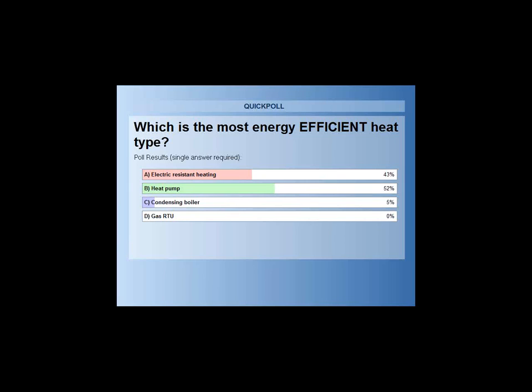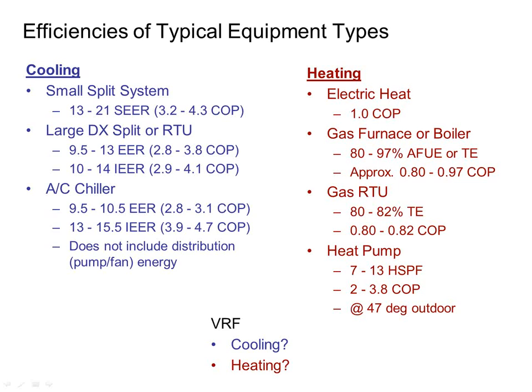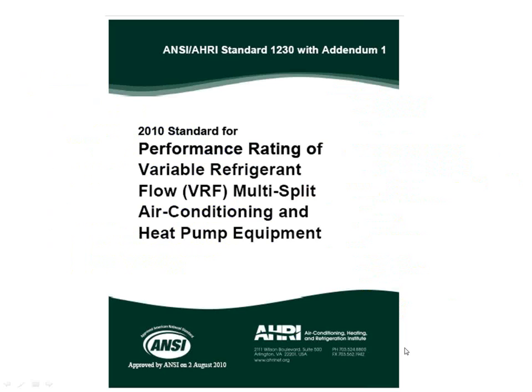Let's just go back one screen here. What was electric resistance heating? A COP of 1. What is heat pump heating? A range on this of 2 to 3.8, right? So heat pumps, even when it's very cold out, like 17 degrees, are twice as efficient as electric resistance heating. Heat pumps always beat electric resistance heating. The worst heat pump in the world on a minus 20 degree day is very likely still going to be over a 1.0 COP. So heat pump is always going to beat electric resistance from an energy standpoint. So I don't know if I tricked you guys with that question on accident or what happened there. Let's go ahead and take that back off. All right, let's continue on.